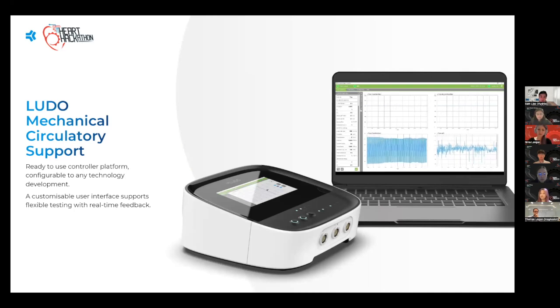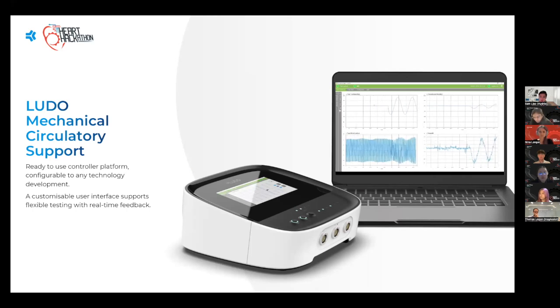So generally, the development of pumps will be performed with off-the-shelf components and controllers, which often have components in the system that are a black box. This approach may be perfectly fine as a proof of concept, but a regulator in the future will want to know everything that is driving the pump. This includes both the software and hardware, and to see that the risk has been managed appropriately. If you don't know what's happening, you can't really manage the risks.